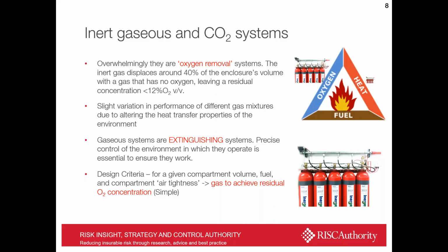There is some slight variation in the performance of the different gas mixtures, because when you introduce additional quantities or when you change the makeup of air, it transports heat differently. So there are some differences in performance between the inert gases, but they are very minor. Gaseous systems can't really be suppression systems. They need to extinguish the fire in order to fulfill their remit. And for that, obviously inherent in the design will be precise control over the environment in which they operate. So we need to ensure that the compartment is sealed so the gas doesn't just dissipate out. We need to ensure that at the time of discharging the gas, we don't destroy the enclosure.